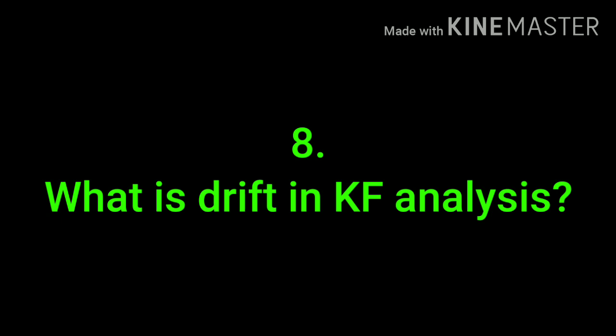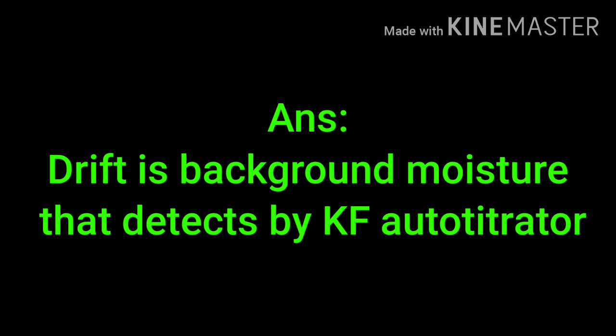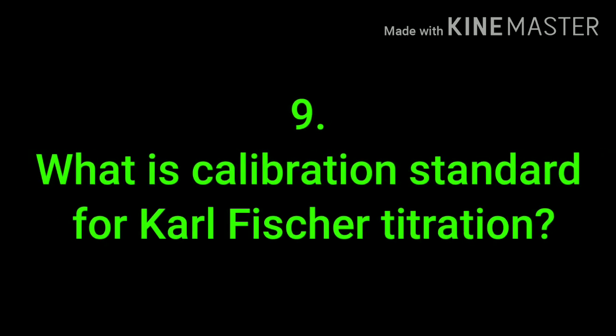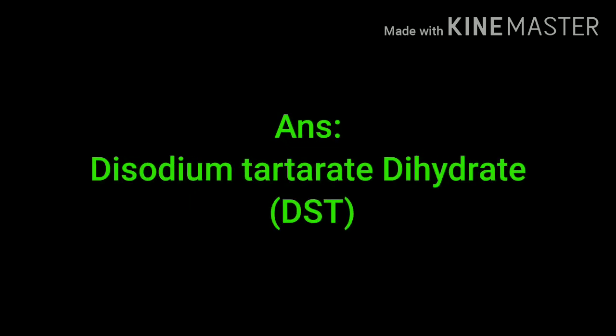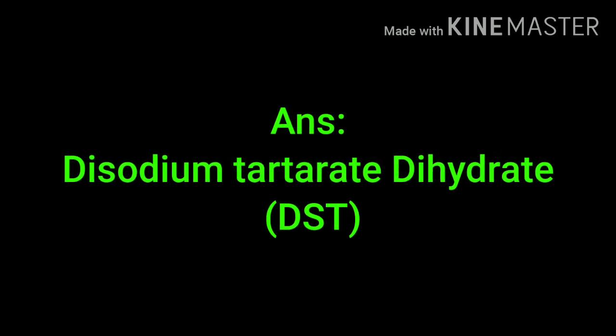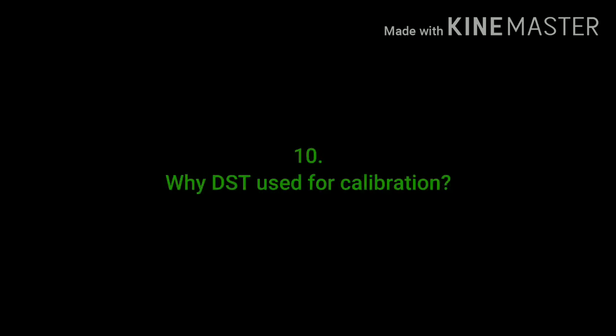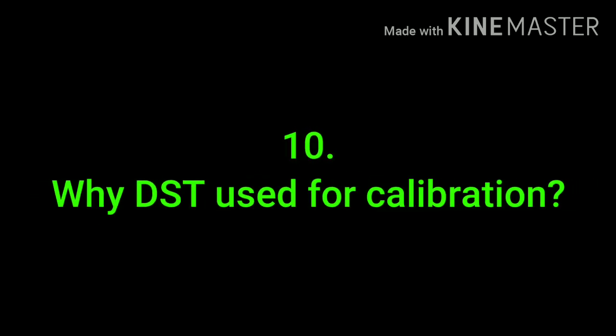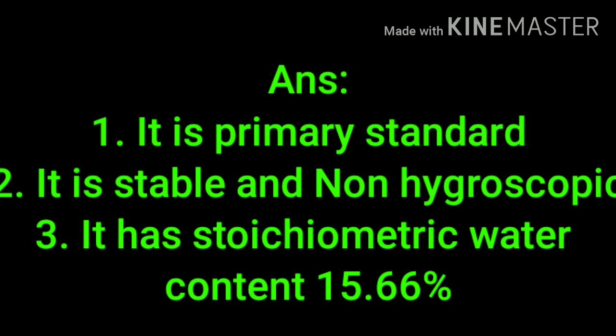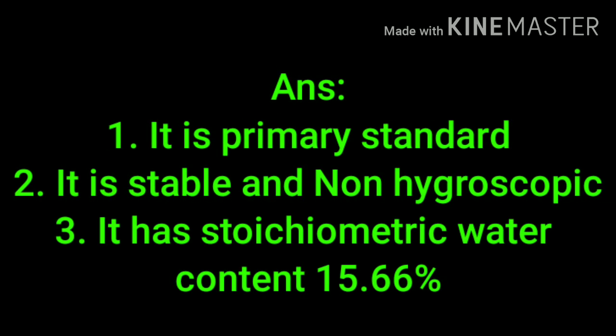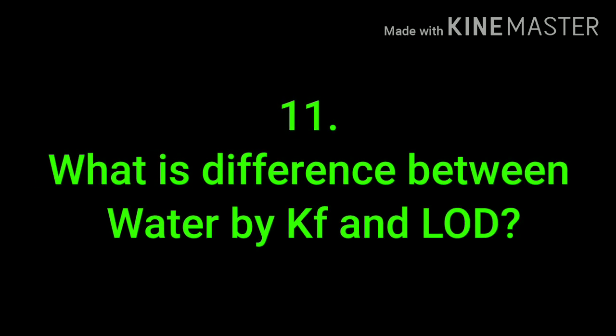What is drift in KF analysis? Drift is the background moisture detected by the KF auto titrator. General analysis will start only when the drift is stable. What is the calibration standard for Karl Fischer? The calibration standard is disodium tartrate dihydrate (DST). DST is used for calibration because it is a primary standard, it is stable and non-hygroscopic, and it has a stoichiometric water content of 15.66 percent.